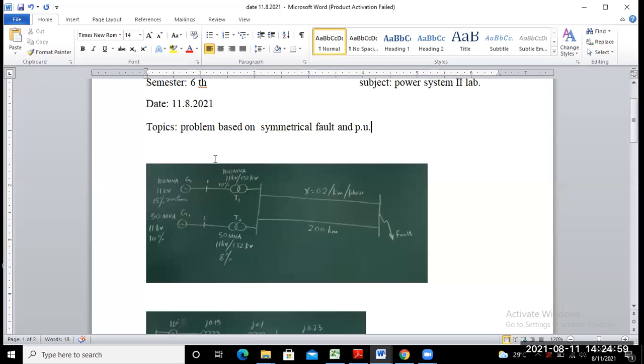Suppose you consider one problem. A power system consists of two generators. Their rating is specified here. Generator 1 is 100 MVA, 11 kilovolt, 15% reactance. Generator 2 is 50 MVA, 11 kilovolt, and 10% reactance. Generator 1 and 2 are connected with transformer 1 and 2 respectively. Transformer 1 and 2 also have their ratings specified here.